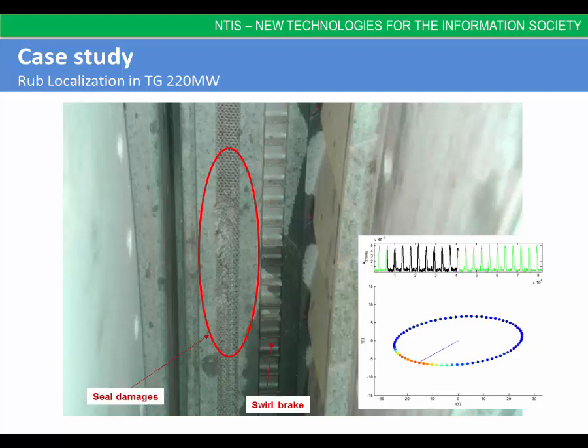Except the axial localization, there is also a need to localize the contact place on the circumference of the turbine stator. An approximate tangential localization is possible when using signals from both absolute stator and relative shaft vibration sensors. When fusing information from sensors of absolute and relative vibrations, the angle of the maximum rubbing intensity can be obtained. The method is based on the representation of rotor motion in the measured plane, from which an orbit of the rotor motion is reconstructed. The time behavior of mean amplitudes in selected frequency bands can be taken into account when rendering the filtered orbit, and time synchronization is ensured by the key phaser.